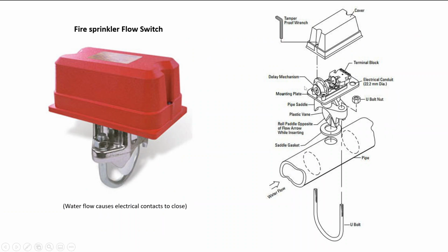Usually there is a time delay mechanism in it to avoid a false alarm. This flap down here is inside the pipe in the path of the water. It is very flexible and plastic, which means when water pushes against it, it will move and set off a trigger or contact inside the mechanism up here. If there was a bit of a pressure wave in the water, we would not want the fire alarm panel to think that there was flow of water and go into alarm. Instead, there's a time delay feature, which an individual can then set, and the setting is usually anywhere from like 5 to 15 seconds. So the flap has to be pushed by flow of water for at least 5 to 15 seconds before the contacts close, in which case the signal is then transmitted to the fire alarm panel.